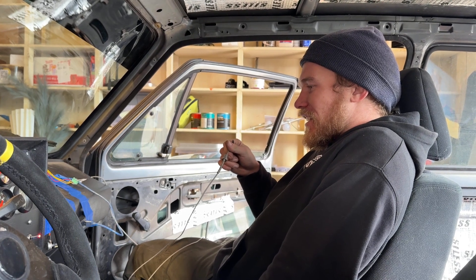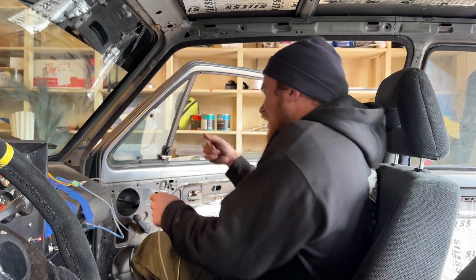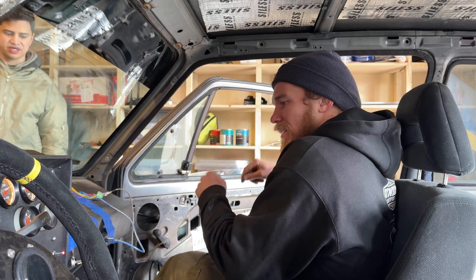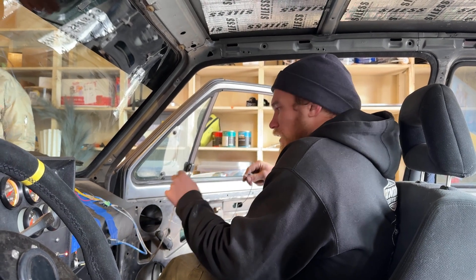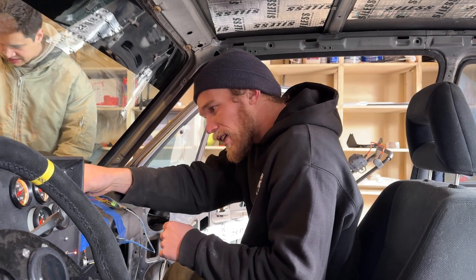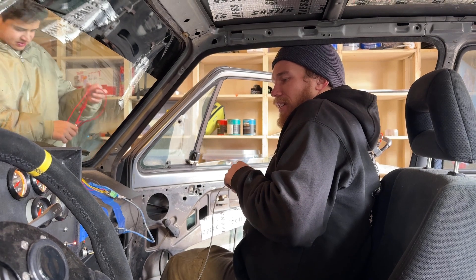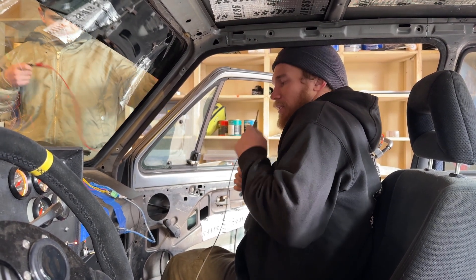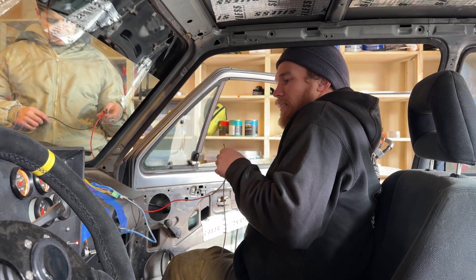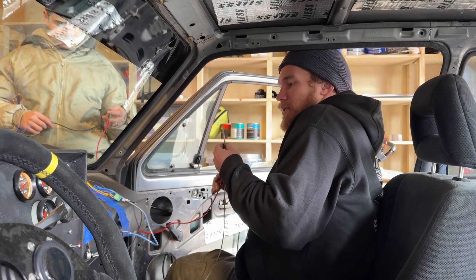So the thermocouple was bad. Something is — I guess the metal jacket doesn't insulate properly. There's like a wire exposed in the metal jacket itself that's touching the middle jacket. Can you throw me a ground? It's reading 65, which seems a little high... straight back to 32.